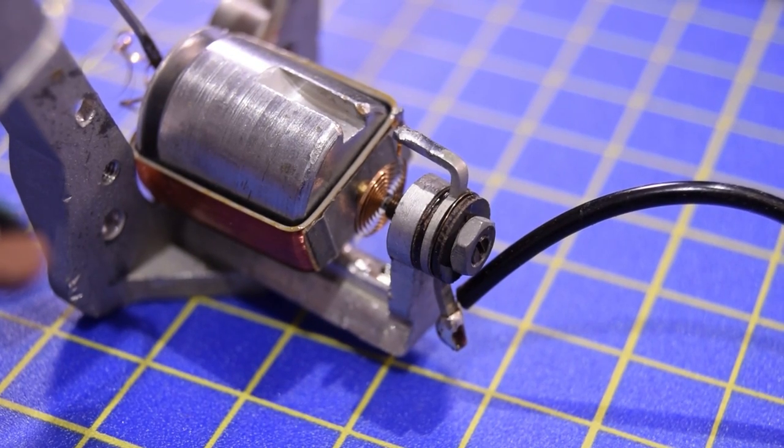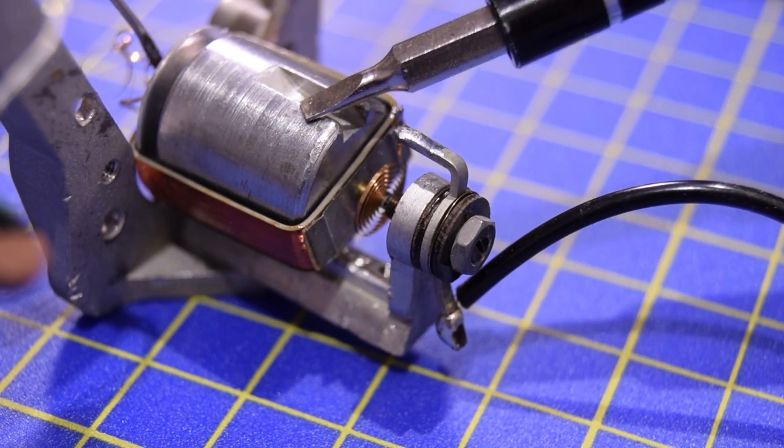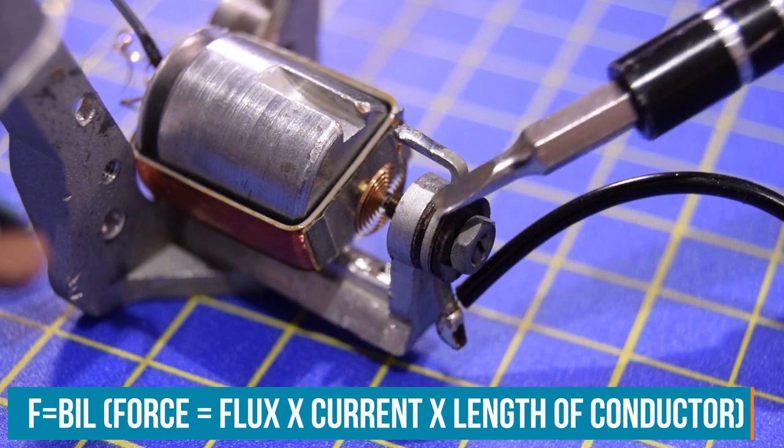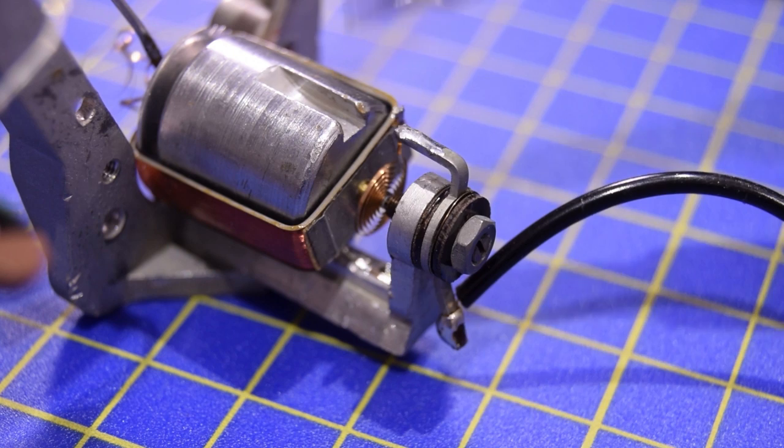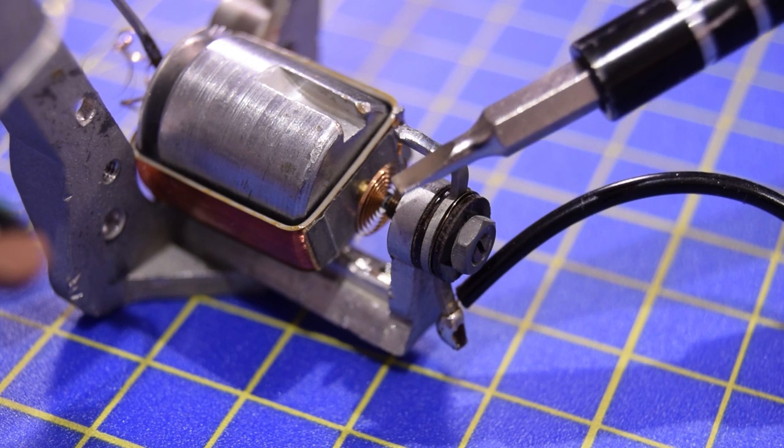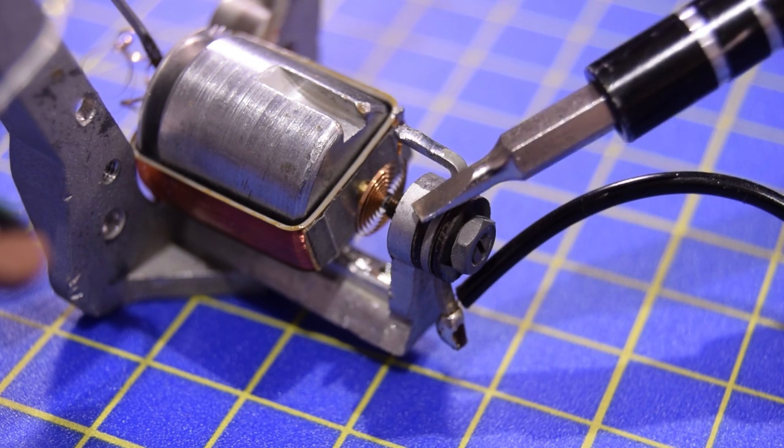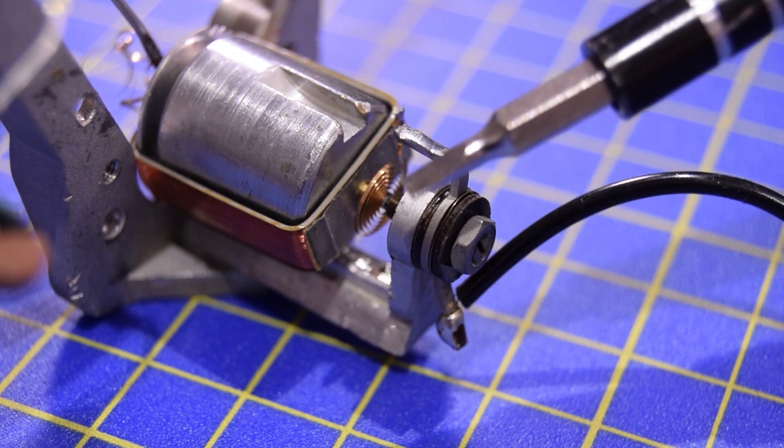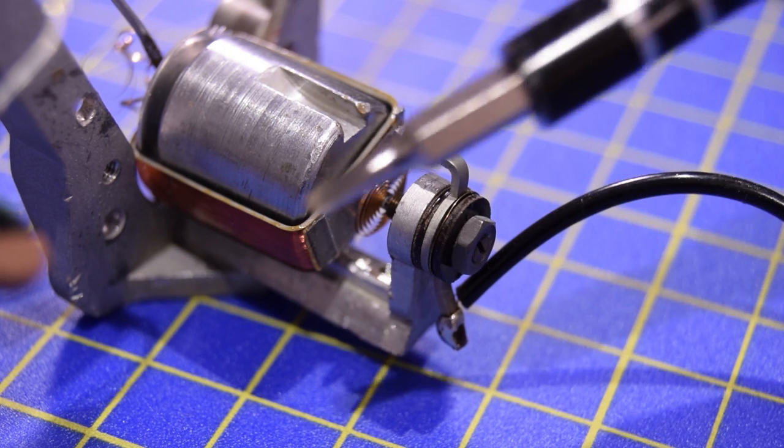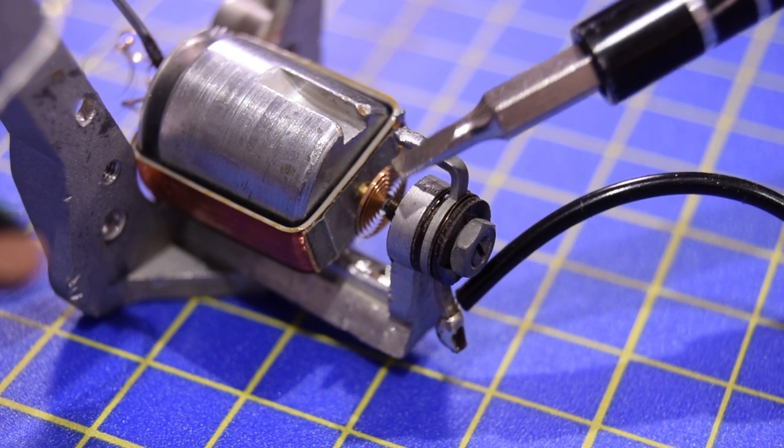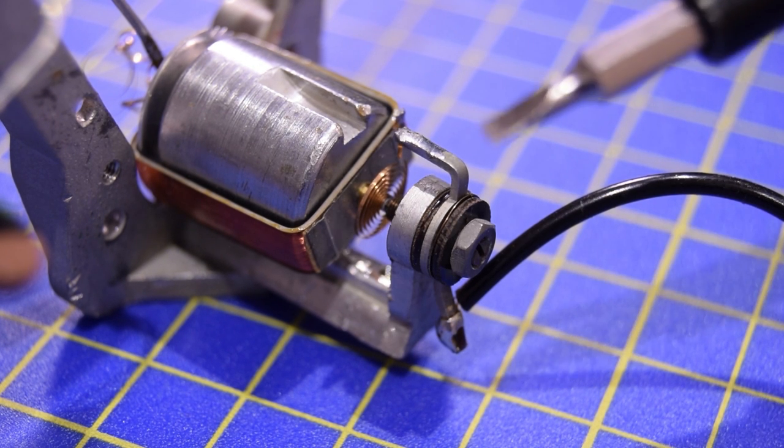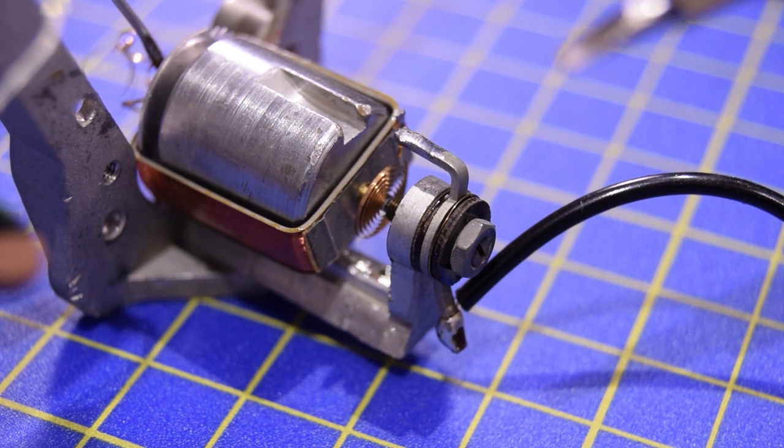So the way this actually functions, if you remember that this cylinder is actually positioned between two permanent magnets. You've got the current that comes in this wire through this assembly and down a tiny little pin which just holds this rotating drum at just a pinpoint right in the center of this spring. But that spring not only gives it the resistance to most motion but is also the conduction path that pulls the electricity from the outside to the inside. With the analog measurements you've got to bear in mind that there's all kinds of friction, there's the resistance to motion, there's work hardening of the metal. You can see how many things have got to go right to give you a decent measurement.